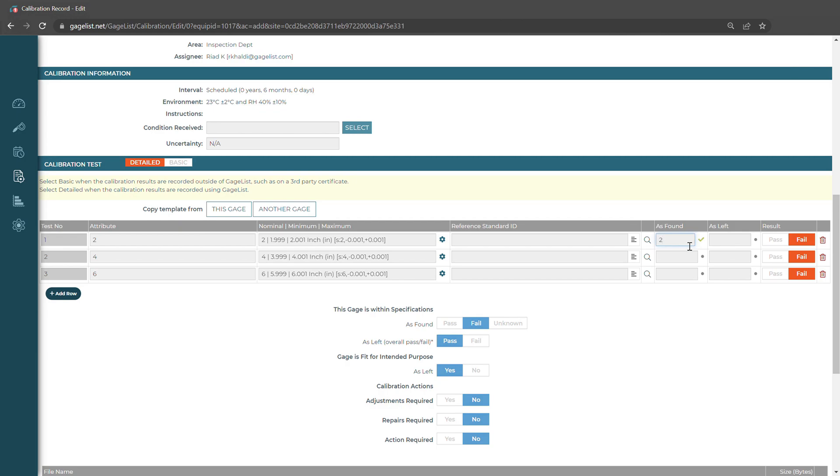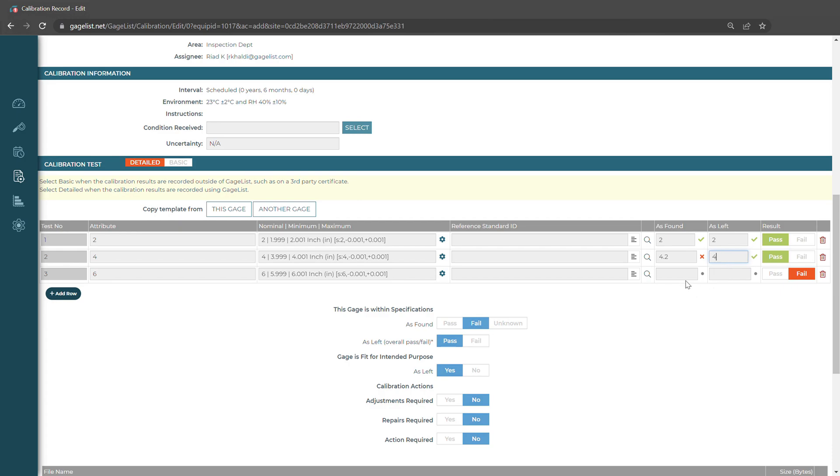If the as found data is within spec, we'll get a checkmark. Same with our as left, it'll give us a passing result. But if it's out of spec, a little flag indicates it isn't correct. But if we zero it back out to a correct nominal value, then it'll pass.